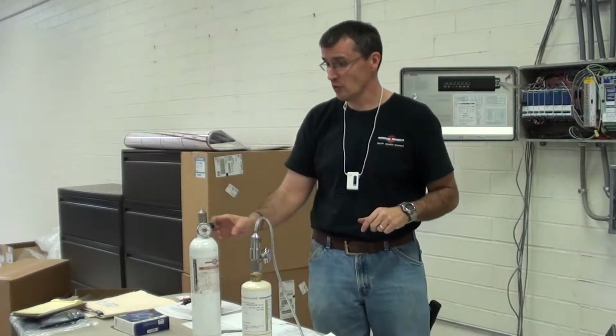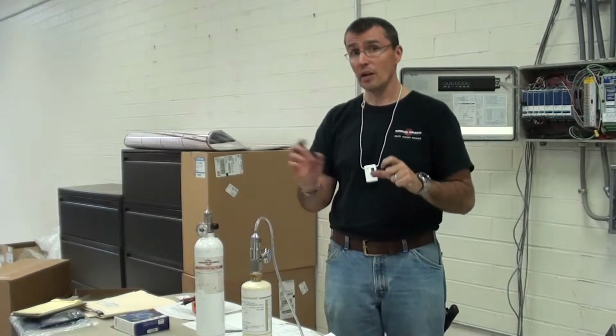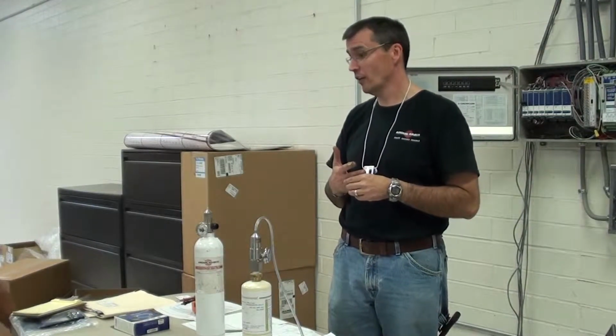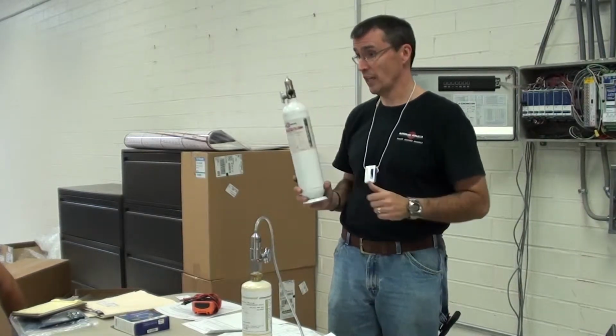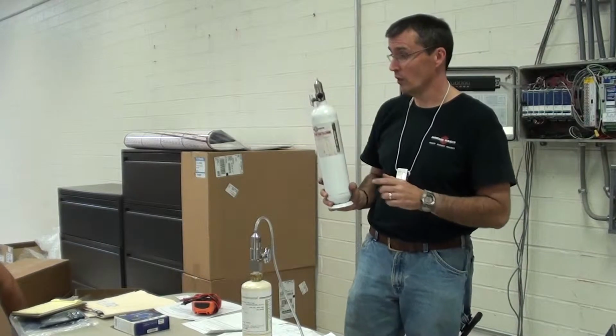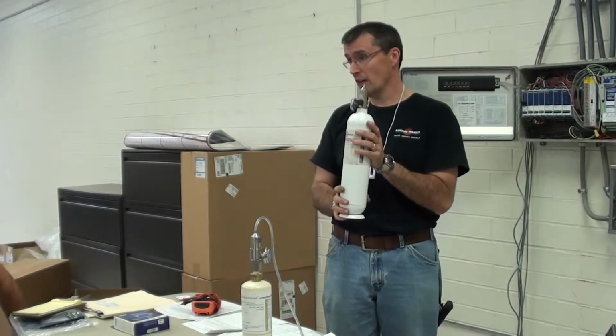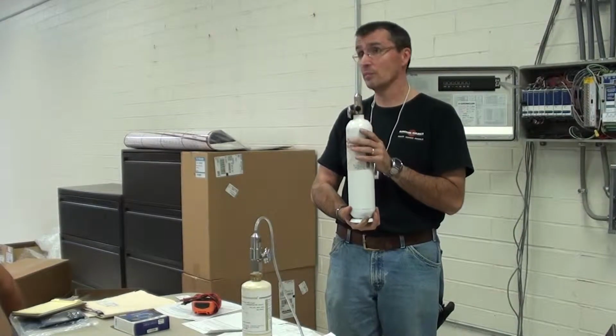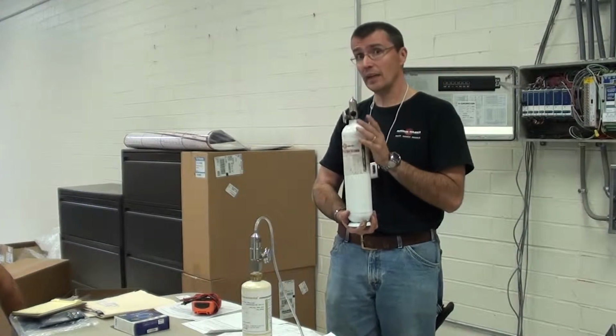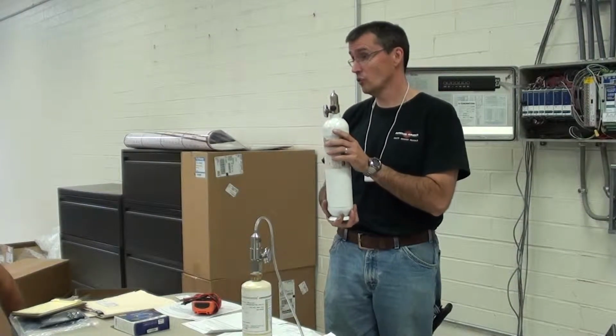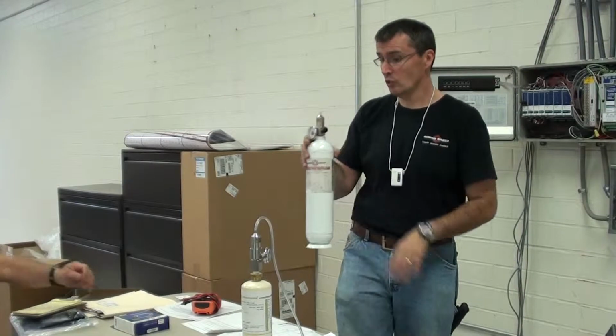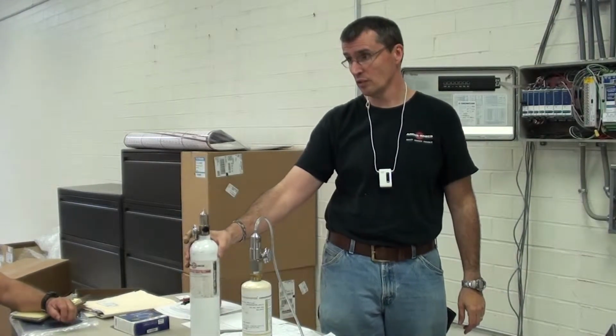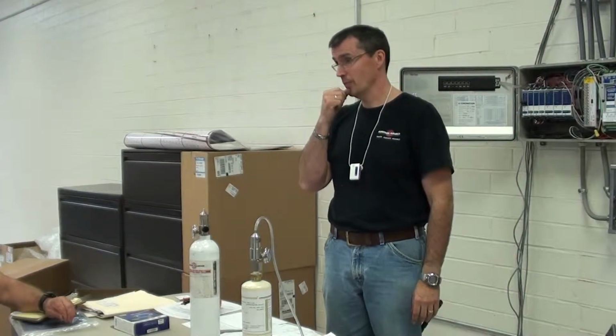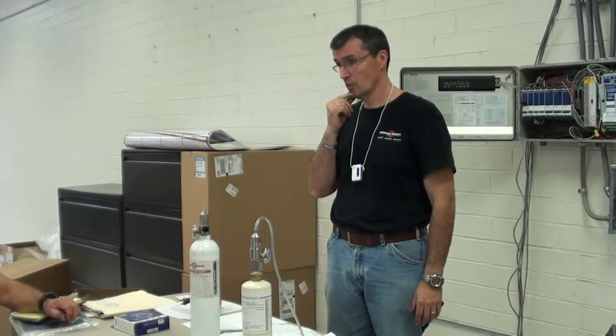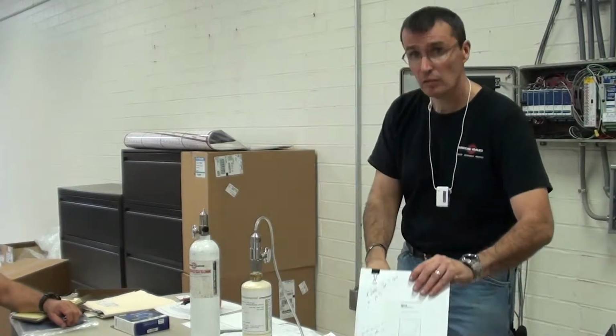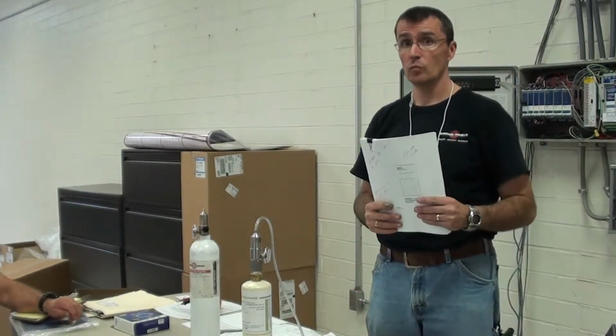But before we do a span calibration, we're always going to zero the transmitter. And because we may be concerned about contaminants in your area, we're always going to expose that sensor to a purge gas. Okay? So this is important as well. When you order a zero gas, if you call a manufacturer and say zero gas, sometimes they'll send you 100% by volume nitrogen. Again, it's recommended that you have air even in your zero cylinder. So you'll see the cylinder that I use is 20.9% by volume oxygen, balanced in nitrogen. Okay? So that's my zero gas. What was that percentage? 20.9. Which is clean ambient air.